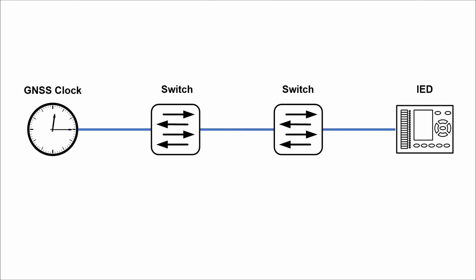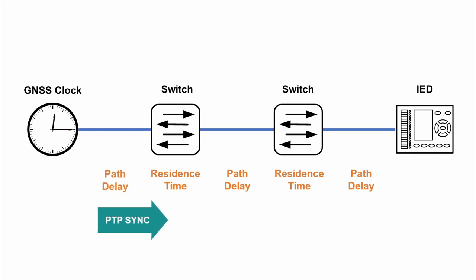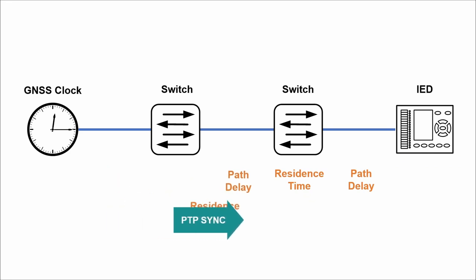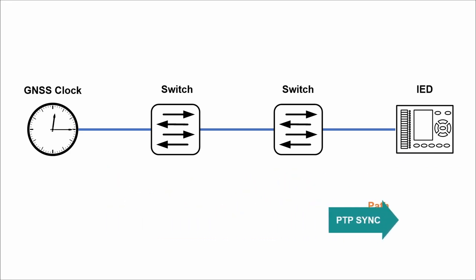In a typical substation application, every switch along the path of synchronization measures path delay of every link and time the packet spends inside the switch. These accumulated delays are written directly into the correction field which allows time clients to calculate time offset very precisely.